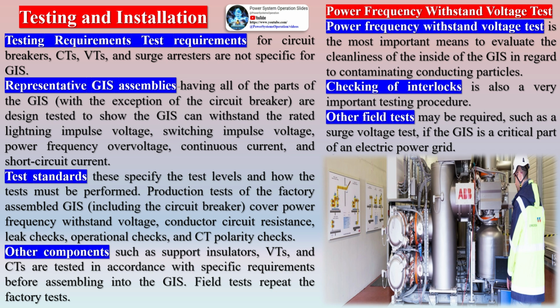Testing requirements. Test requirements for circuit breakers, CTs, VTs, and surge arresters are not specific for GIS. Representative GIS assemblies having all of the parts of the GIS with the exception of the circuit breaker are design tested to show the GIS can withstand the rated lightning impulse voltage, switching impulse voltage, power frequency overvoltage, continuous current, and short circuit current. Test standards. These specify the test levels and how the tests must be performed.